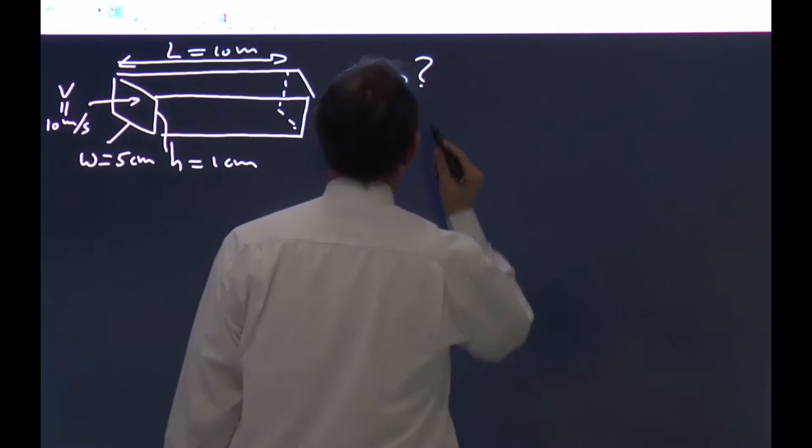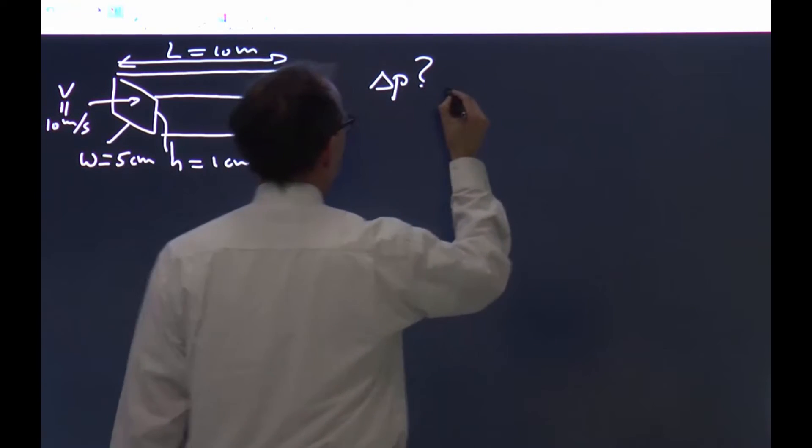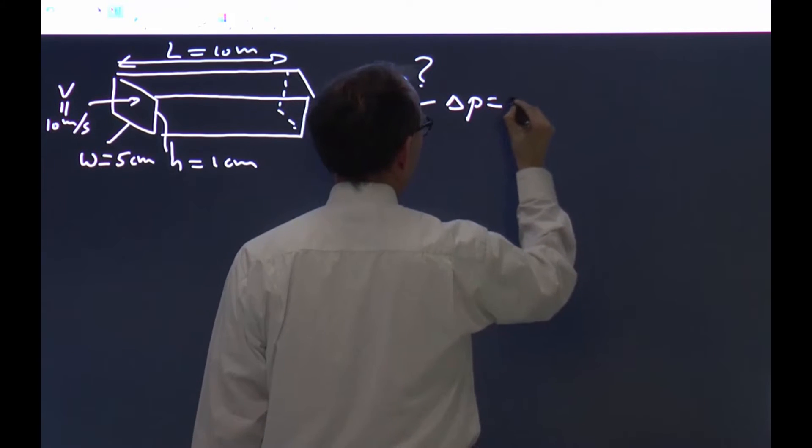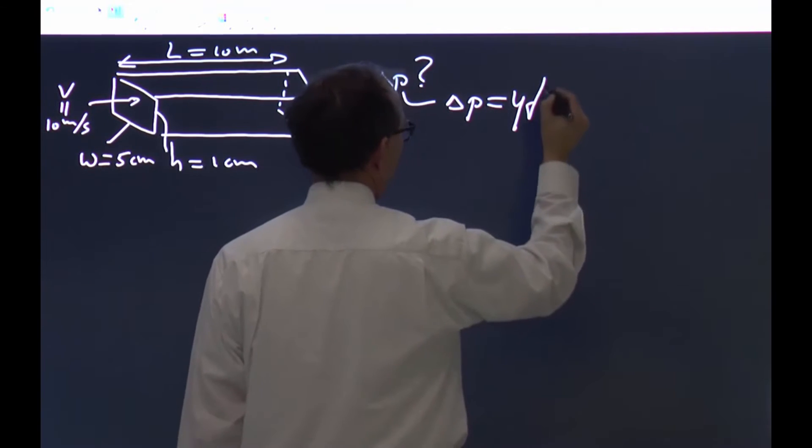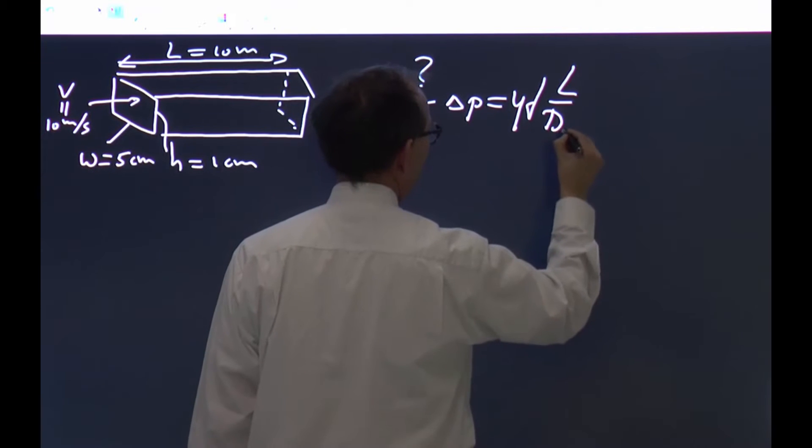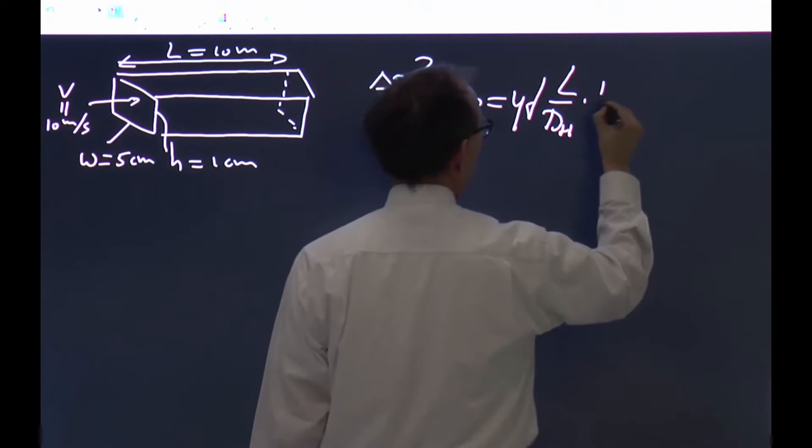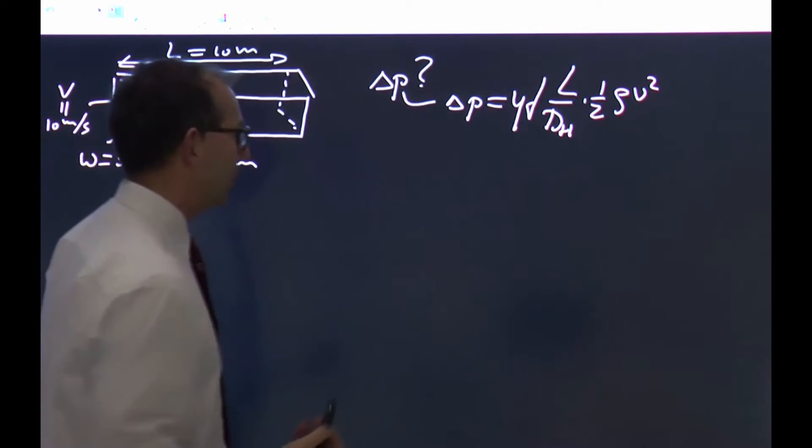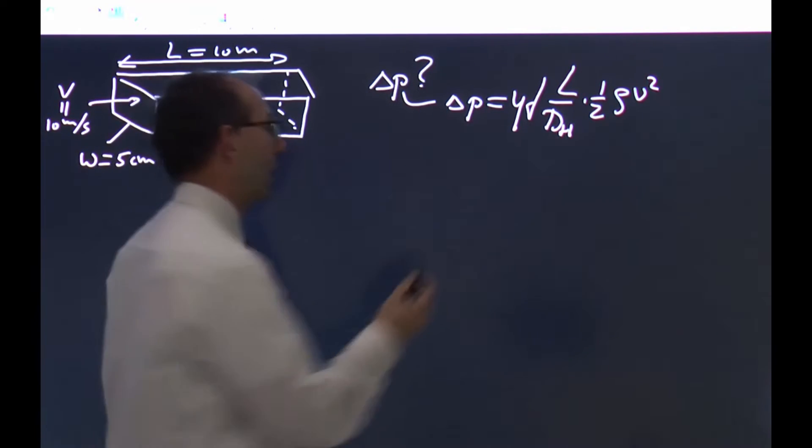Okay, from theory we learned how to do that. Delta p equals 4f, Fanning's friction factor, length over hydraulic diameter times half rho v squared. The point here is twofold. One, we need to find the hydraulic diameter.